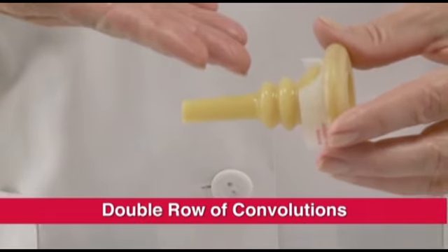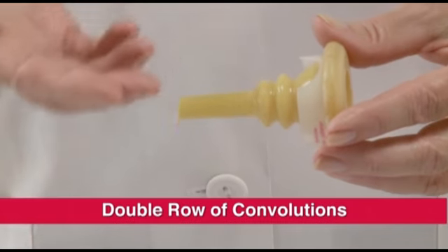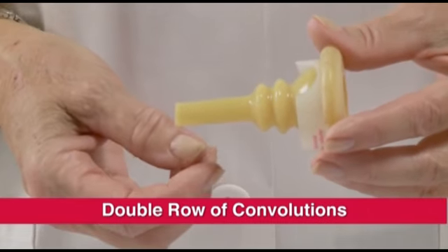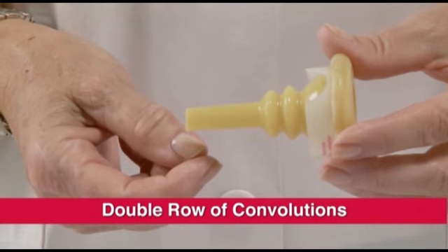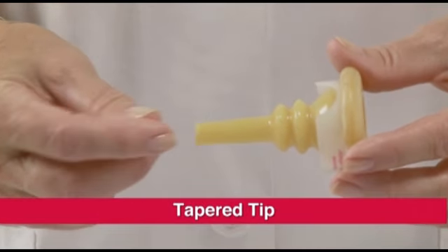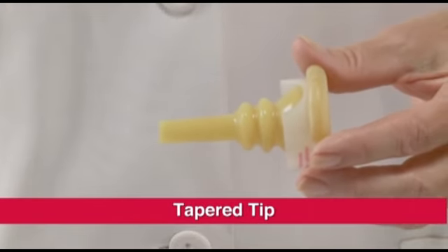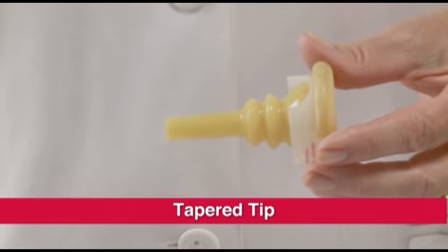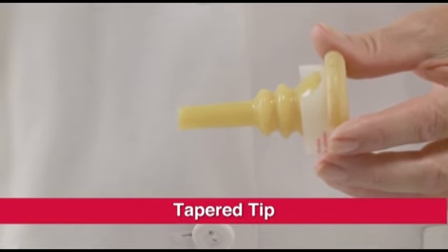loosening the catheter. The double row of convolutions near the catheter tip is designed to prevent kinking and twisting, so the fluid pathway can remain open and can drain freely. Finally, the tapered tip helps to provide a secure connection to either a leg bag or other urine collection system.